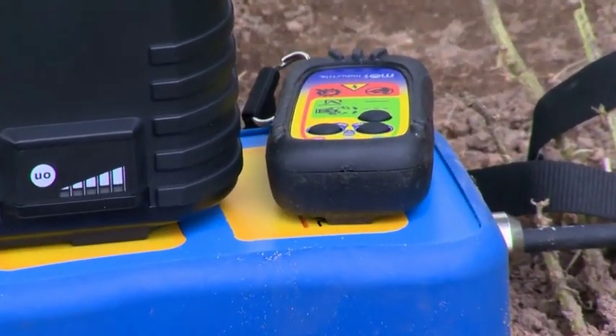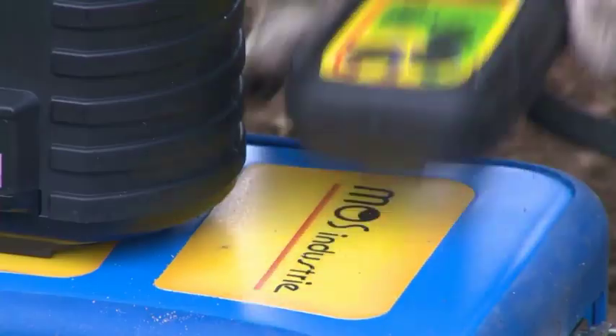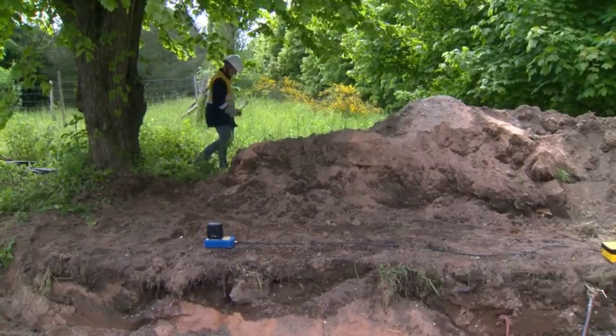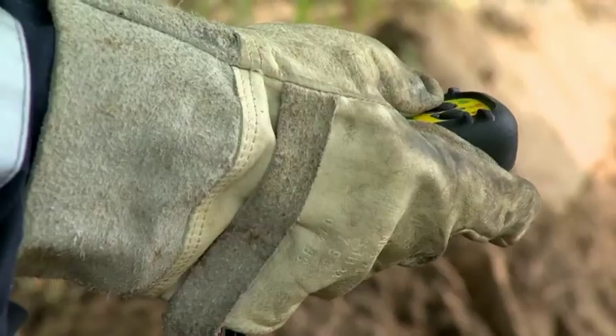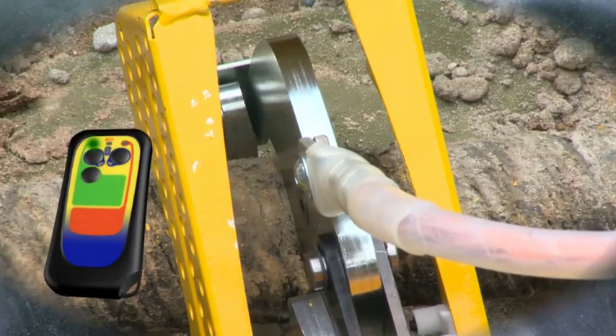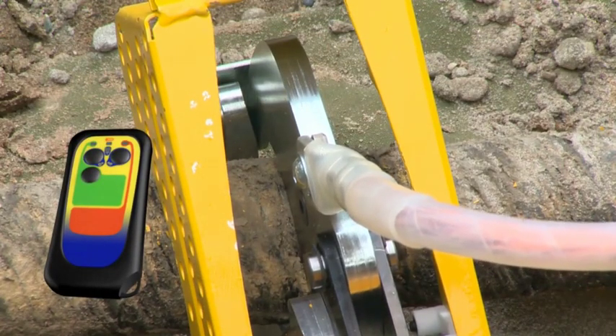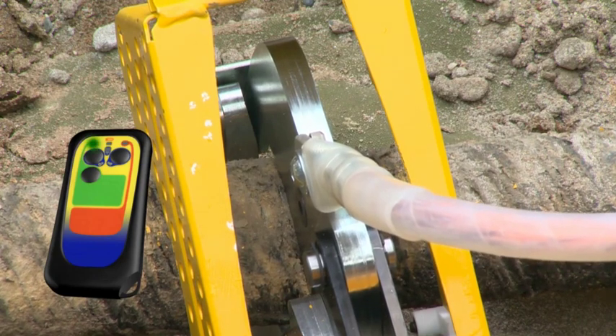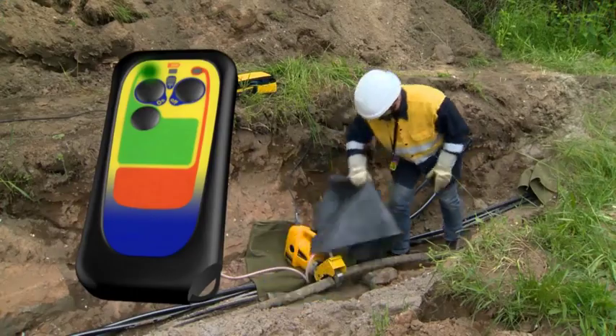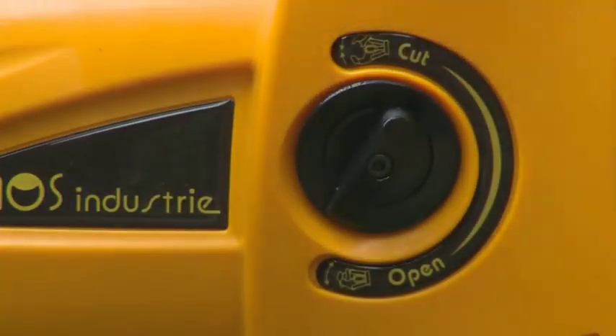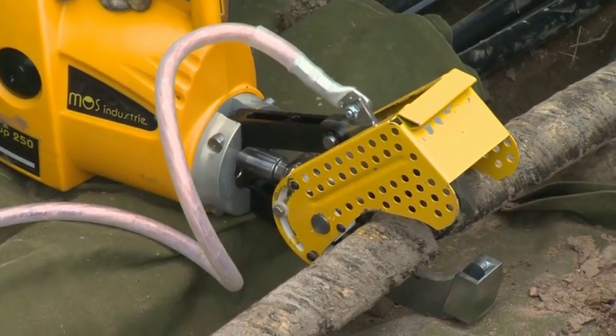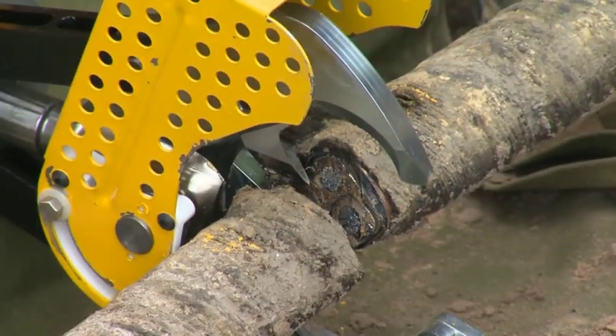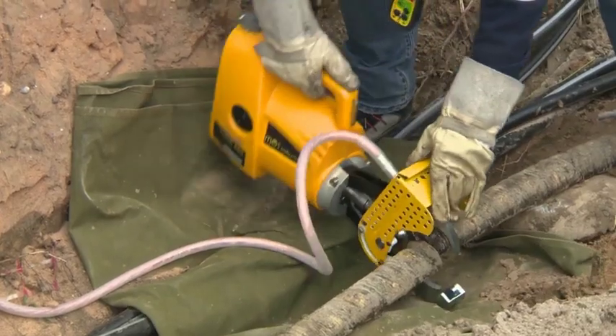Next, the P-Coupe is remote controlled and enables you to cut the cable while limiting consequences of cable spiking on the wrong cable. In addition, in order to avoid incomplete spiking, the P-Coupe then automatically completely cuts the cable. Maximum precautions have been taken to ensure the right cable has now been cut.